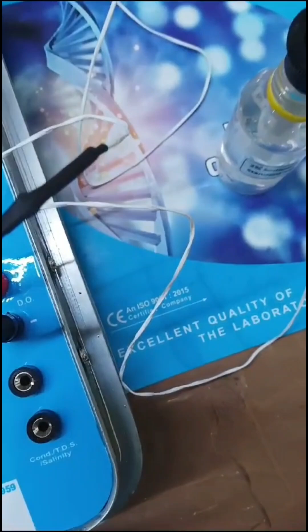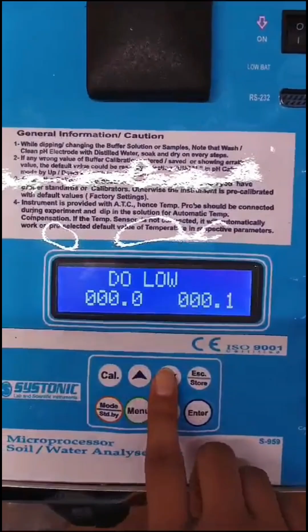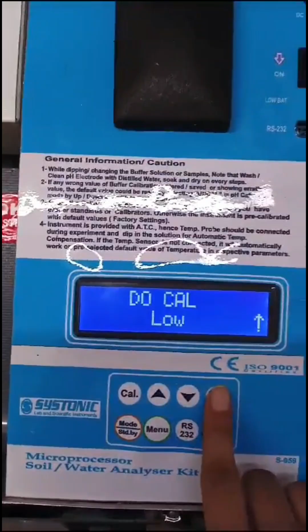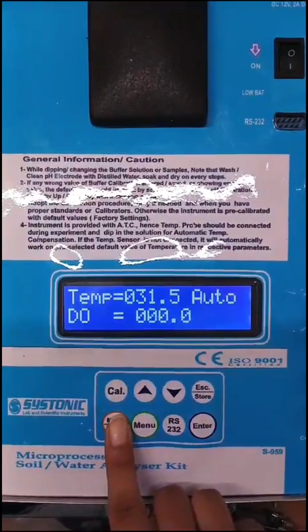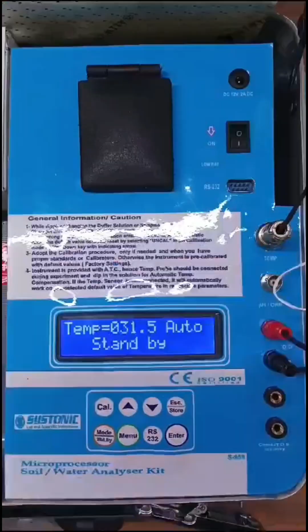So go to cal again and on DO press enter. First you have to uncal it. After that, go to low, and from here if your value is not near 0, then you can change it through this up and down key and then press enter. After that, go to mode, and from here you can check the value, and it is 0. As it is calibrated now, dip this DO probe in water and you can check the value of DO according to the table given in the manual. So that's how it works.